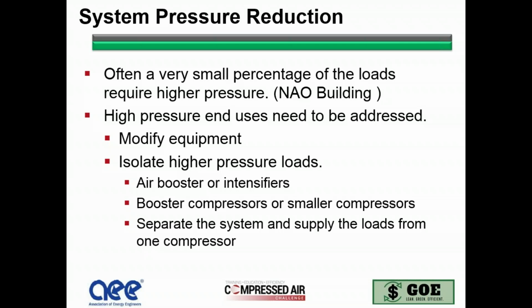And for actual building heat and the requirement of load that they had in the system, they only required maybe 20, 30 PSI at max. So I asked why, and I found out that the reason they did it was that whenever the executives came in and had low pressure on their tires, they needed to pump up the tires. So basically they were wasting all of the time and energy running a much larger compressor than was required. So I had them get a smaller compressor and modify the system to take care of that.